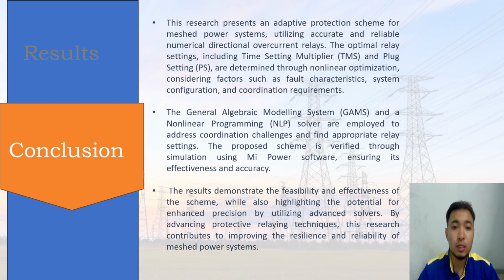The conclusion of this research is that it presents an adaptive protection scheme for a mesh power system utilizing accurate and reliable numerical directional overcurrent relays. The optimal relay settings, including time setting multiplier and plug setting, are determined through non-linear optimization, considering factors such as fault characteristics, system configuration, and coordination requirements. The General Algebraic Modeling System and a non-linear programming solver are employed to address coordination challenges and find appropriate relay settings. The proposed scheme is verified through simulation using MiPower software, ensuring its effectiveness and accuracy.